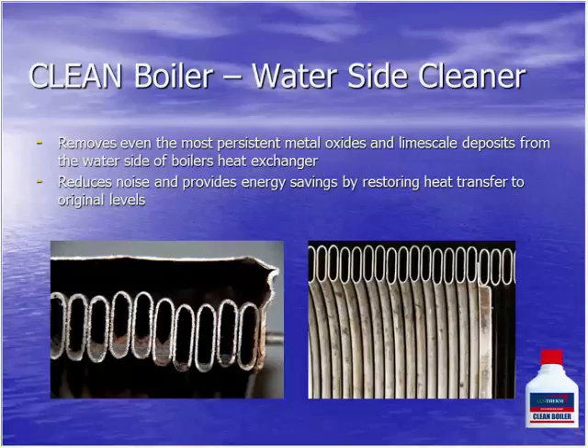We had a local contractor attempt to clean a boiler in a hospital. There was a retrofit that had been done. The contractor came in, changed out the boiler, cut the pipes off, and didn't properly purge and flush the old distribution system. It ran fine for the first winter, but when it came time to fire it up in the fall, the boiler was limiting its firing rate to about 35% because it just couldn't extract enough heat. So he attempted to clean out that heat exchanger with two other chemicals, and then I provided our clean boiler. He went there a week later and let it circulate for about 4 hours. He said you wouldn't believe the stuff that came out of it.